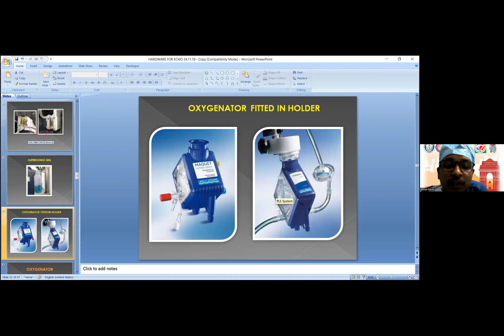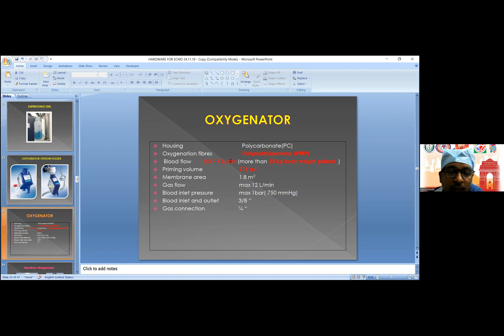The next component is the oxygenator. This is another important component. The natural lungs have a membrane area of 70 square meters, but artificial membranes of 1.5 to 4 square meters are available in the market. Specifically, the Maquet oxygenator is mostly used in most centers because of its simplicity and availability. Its membrane surface area is 1.8 square meters. A maximum of 12 liters of gas flow can be passed. It has a 3/8 connection, through which we can generate 0.5 to 7 liters. But in the Indian population, if the patient is not obese, a standard patient is 50 to 90 kg and requires around 4 to 5 liters of flow.